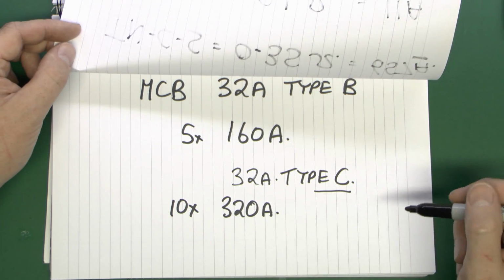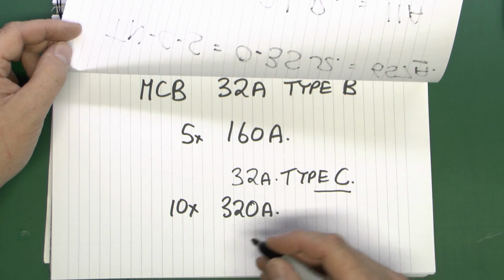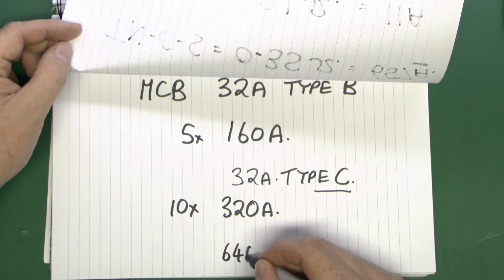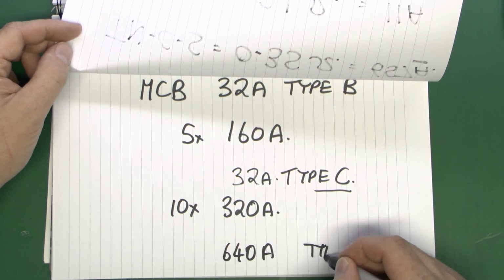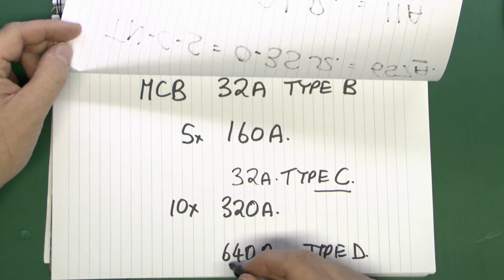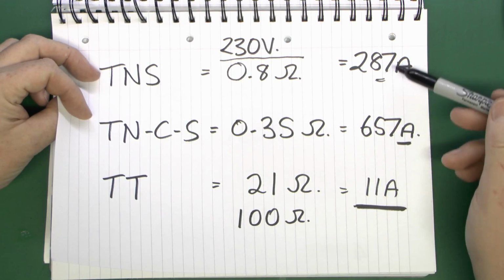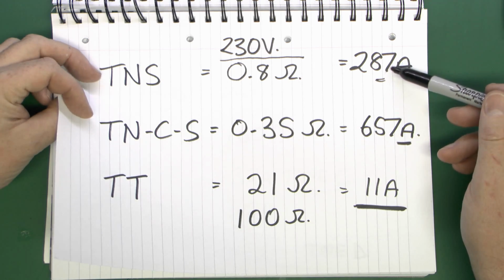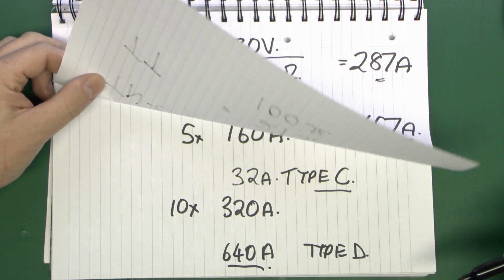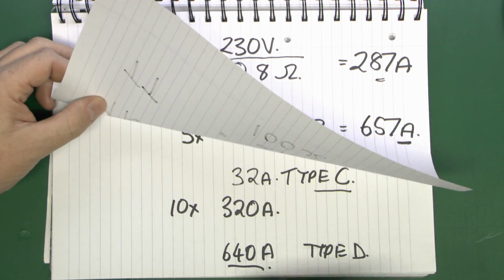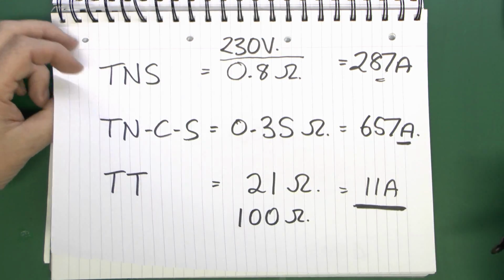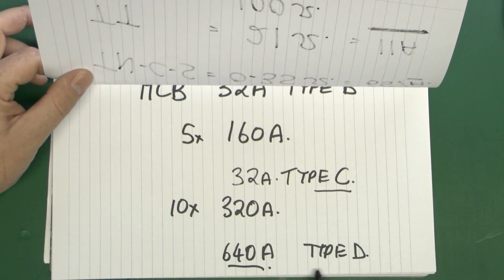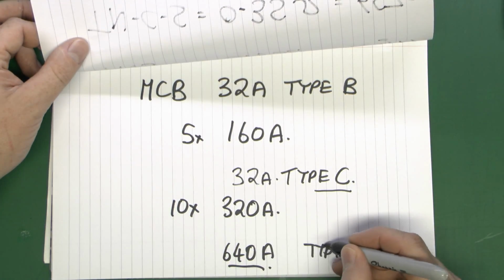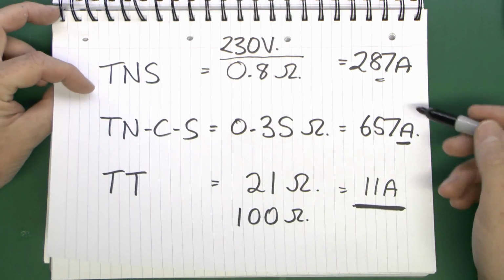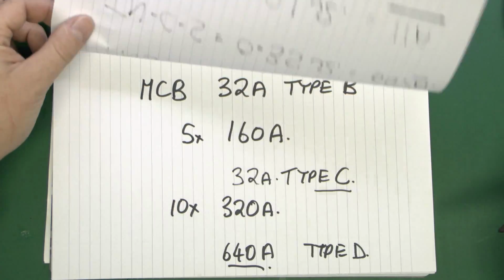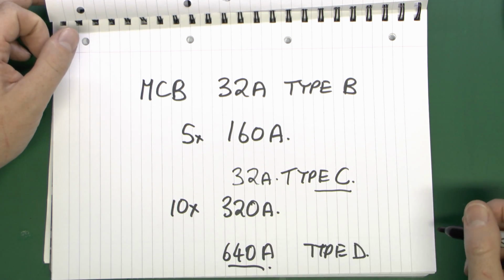And of course there is a type D as well, which requires 20 times the current, and in the case of that one, you would need 640 amps if it was a type D. And as you can see there, that's way off. Clearly 287 is massively less than 640, so pretty obviously not going to work. 657 is just within, so 640 and you've got 657. But again, careful consideration has to be given to using type D's there, certainly of high ratings, simply the fact that the total available current in many cases is not going to be sufficient to trip the device within the required time.